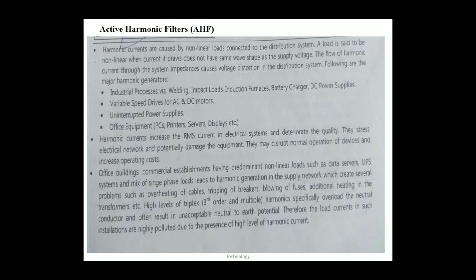Harmonic current increases the RMS current in the electrical system and deteriorates the quality. They stress the electrical network and potentially damage the equipment. They may disrupt normal operation of devices and increase operating costs. Office buildings and commercial establishments having predominantly non-linear loads such as data servers, UPS systems and a mix of single phase loads lead to harmonic generation in the supply network, which creates several problems such as overheating of cables, tripping of breakers, blowing of fuses, additional heating in the transformer, etc.